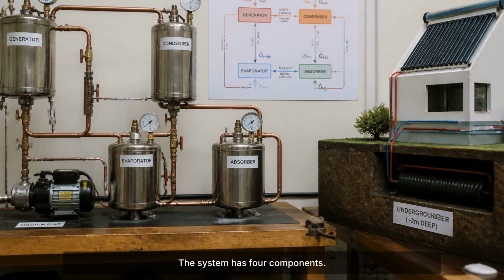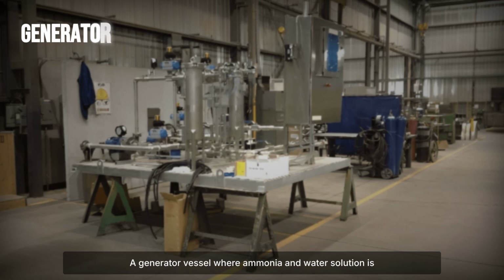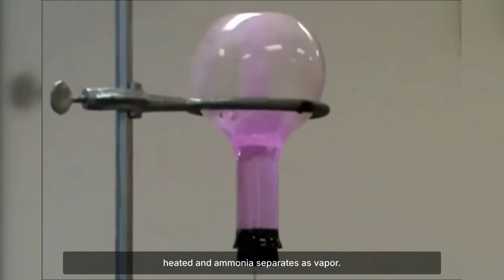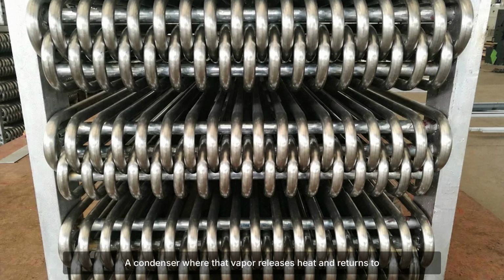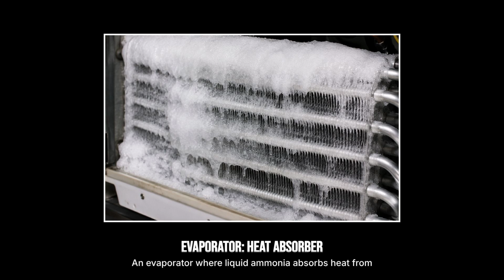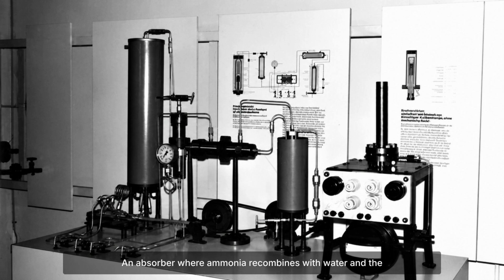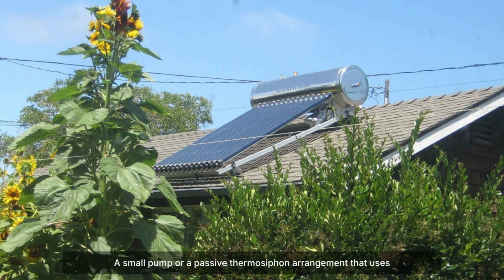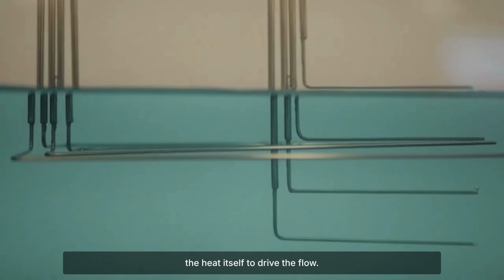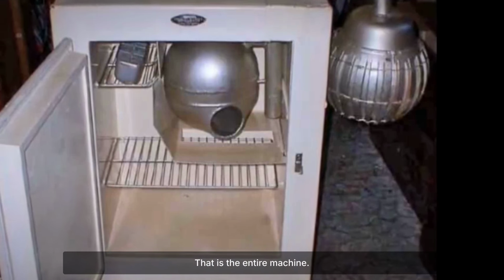The system has 4 components: a generator vessel, where ammonia and water solution is heated and ammonia separates as vapor, a condenser where that vapor releases heat and returns to liquid, an evaporator where liquid ammonia absorbs heat from surrounding air, producing the cooling, an absorber where ammonia recombines with water and the cycle starts over, connecting pipe, a small pump, or a passive thermosiphon arrangement that uses the heat itself to drive the flow. That is the entire machine.